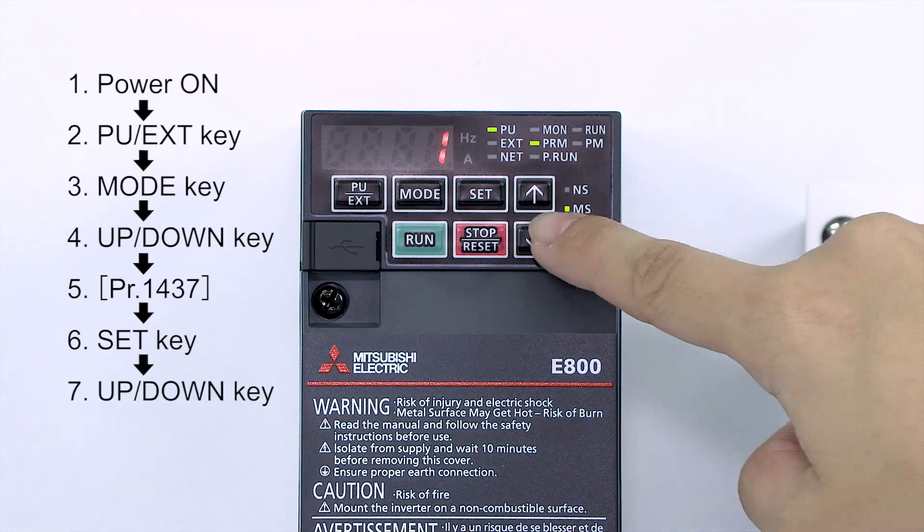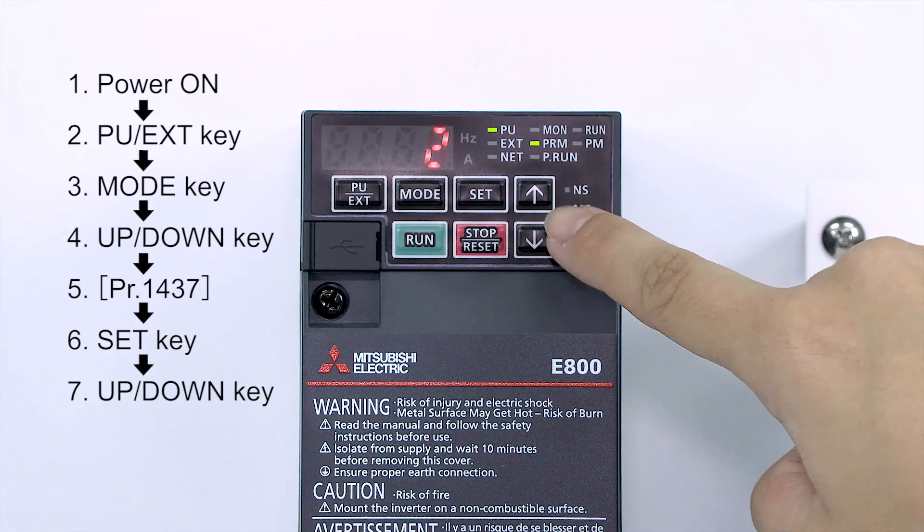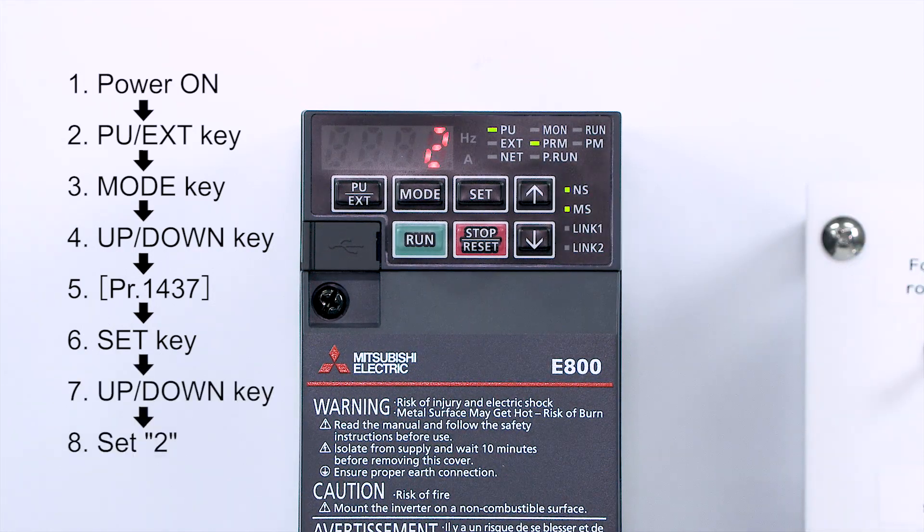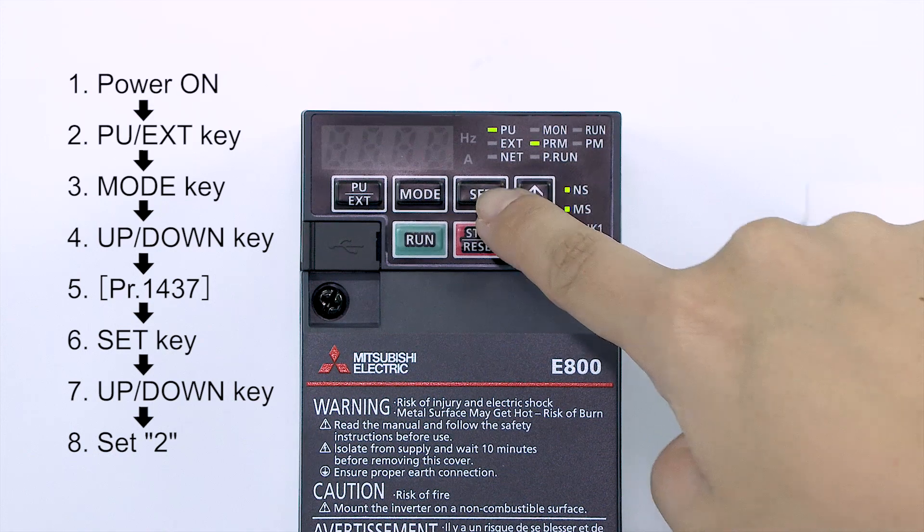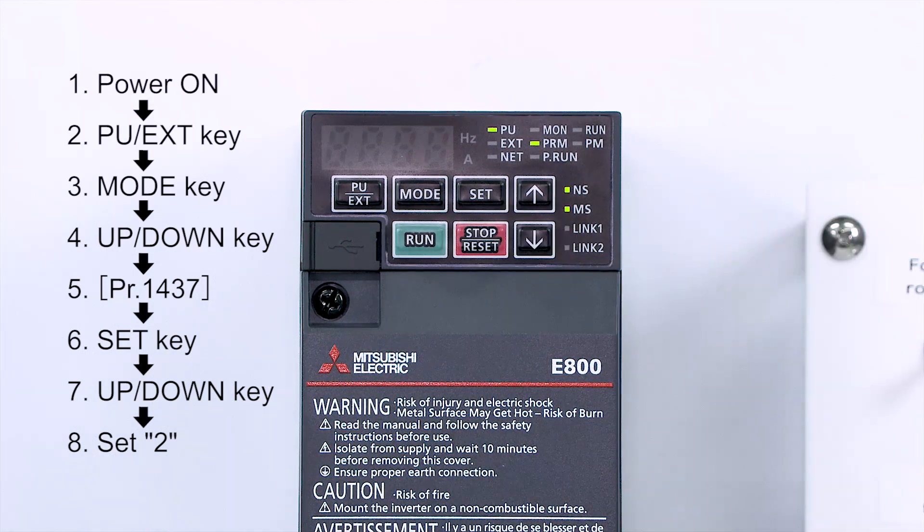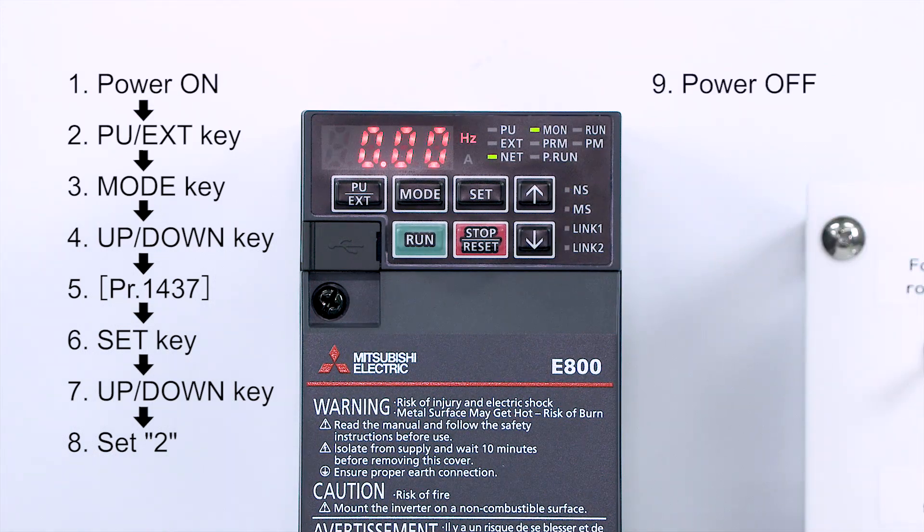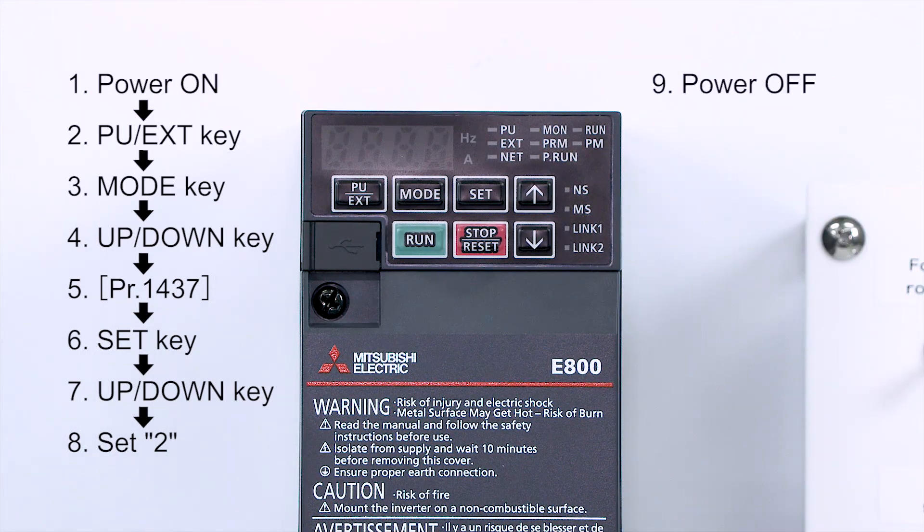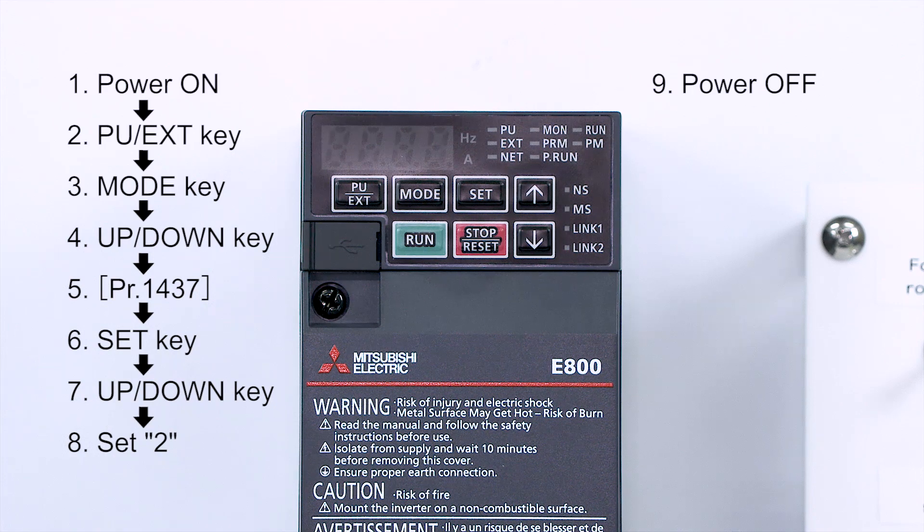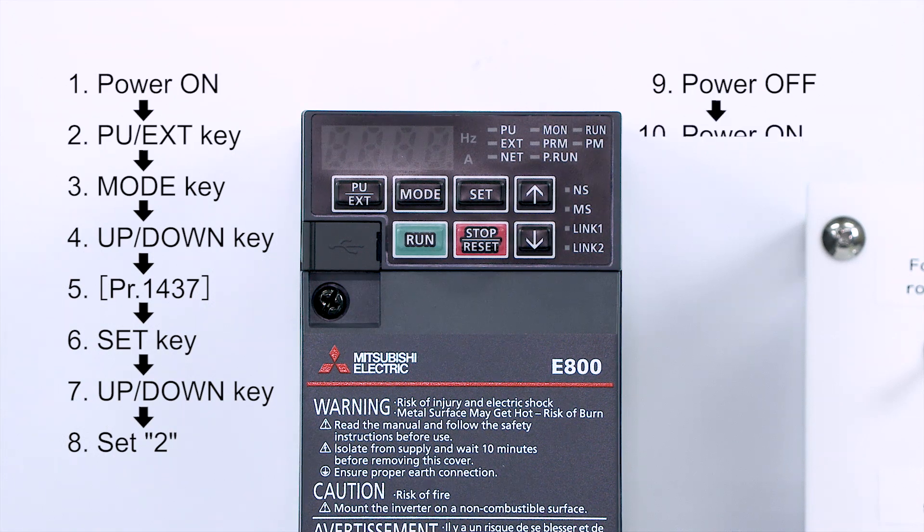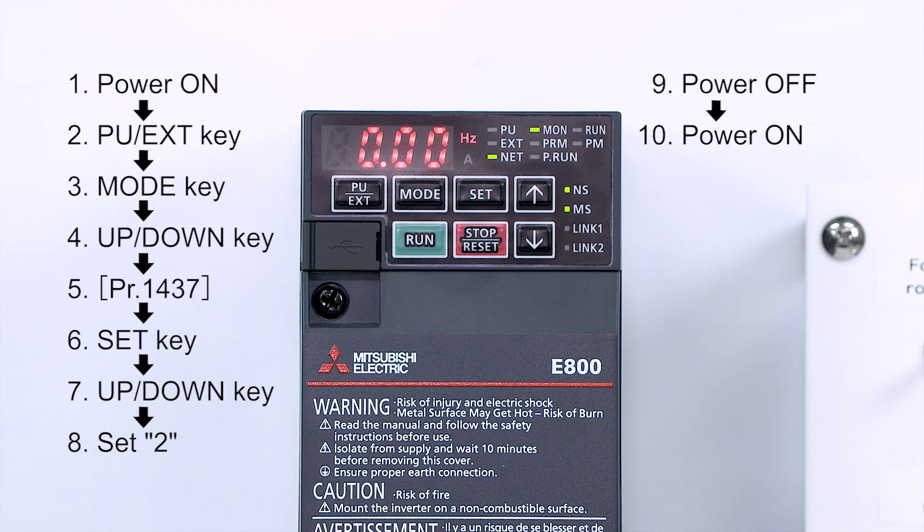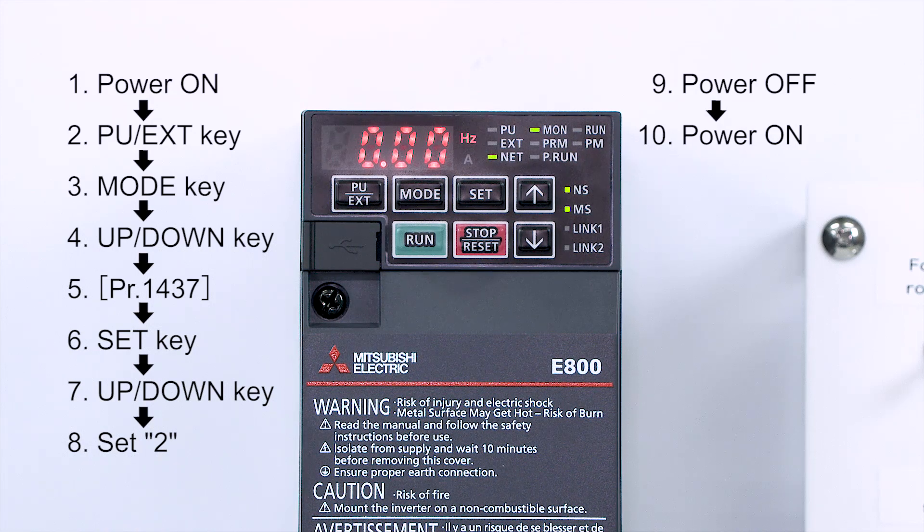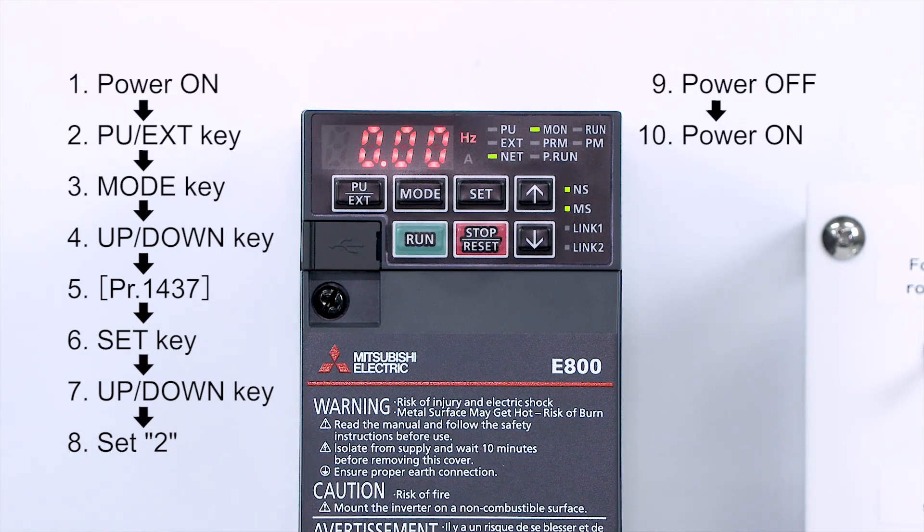Next, select 2 with the UP-DOWN key. Then, turn off the inverter's power. After confirming that the LED display has gone out, turn on the power again. This completes setting the inverter's IP address.